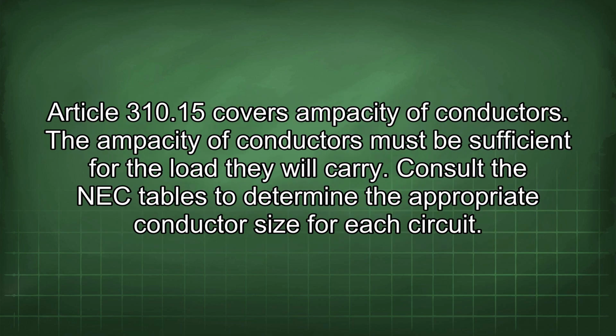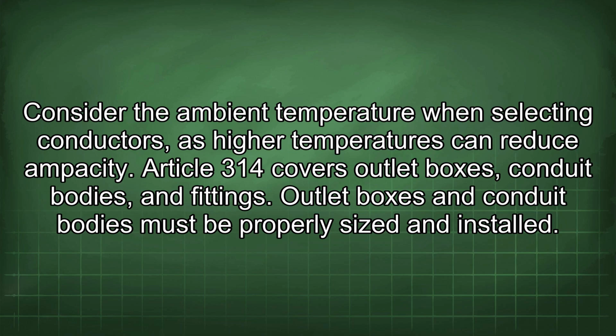Article 310.15 covers ampacity of conductors. The ampacity of conductors must be sufficient for the load they will carry. Consult the NEC tables to determine the appropriate conductor size for each circuit. Consider the ambient temperature when selecting conductors, as higher temperatures can reduce ampacity.